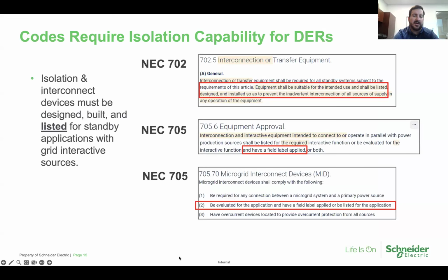Now, okay, we've talked about the fact that we're allowed to use inverter-based sources for emergency power. We've talked about the need for isolation if you are using one of those for both energy optimization and resiliency. But the National Electric Code in numerous spots goes a step further and says that these must be essentially UL listed. The exact phrasing, as you can see here, is the equipment shall be suitable for the intended use and shall be designed and installed to prevent inadvertent interconnection. Should have a field label applied, should be evaluated for the application and have a field label or be listed for the application. So that really means the product needs to be tested and qualified for its specific job.